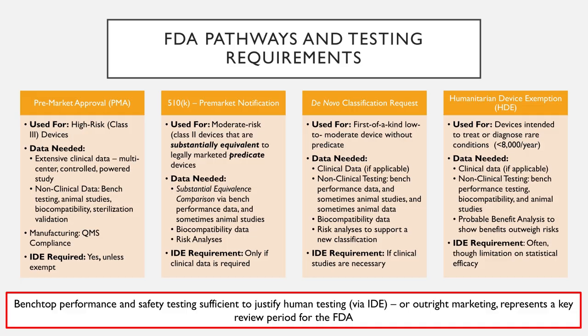And you might do that with definitely benchtop performance tests, sometimes animal studies. You almost certainly have to do biocompatibility studies and certain types of risk analyses that show you've thought through any potential differences or risks inherent to your device. And you might have to do an IDE, particularly if clinical data is required. But again, there might be pathways to justify not having to do those.